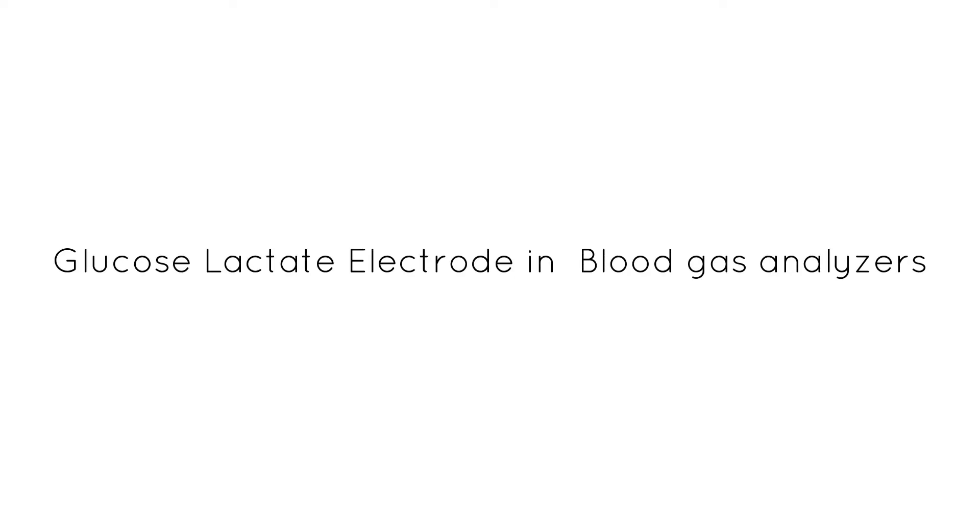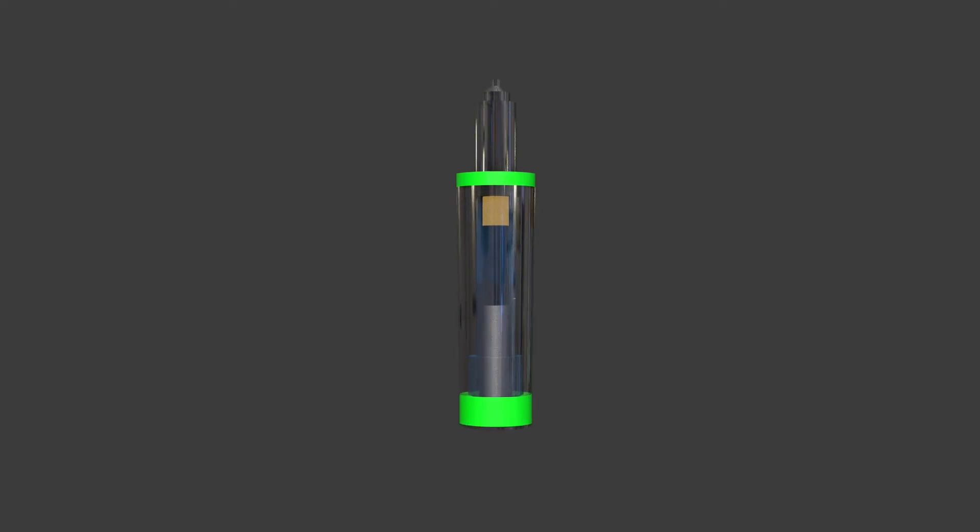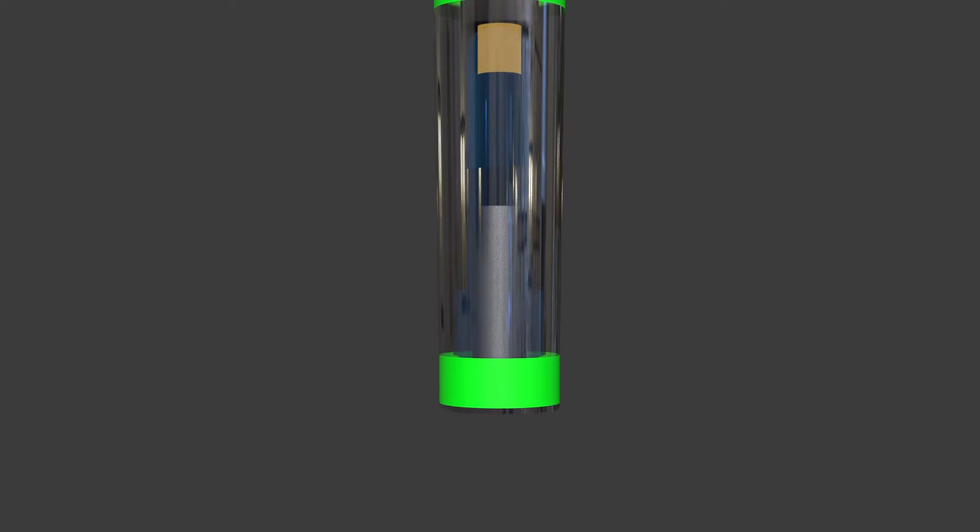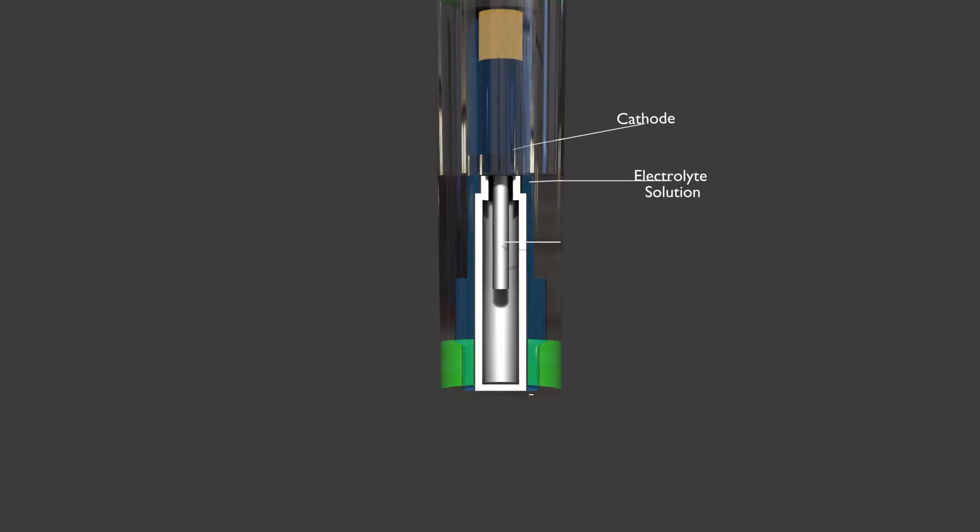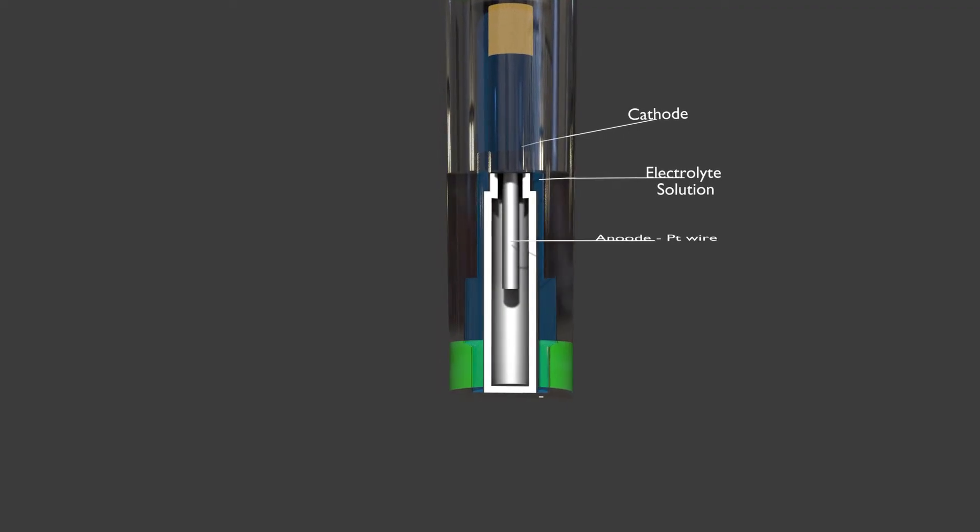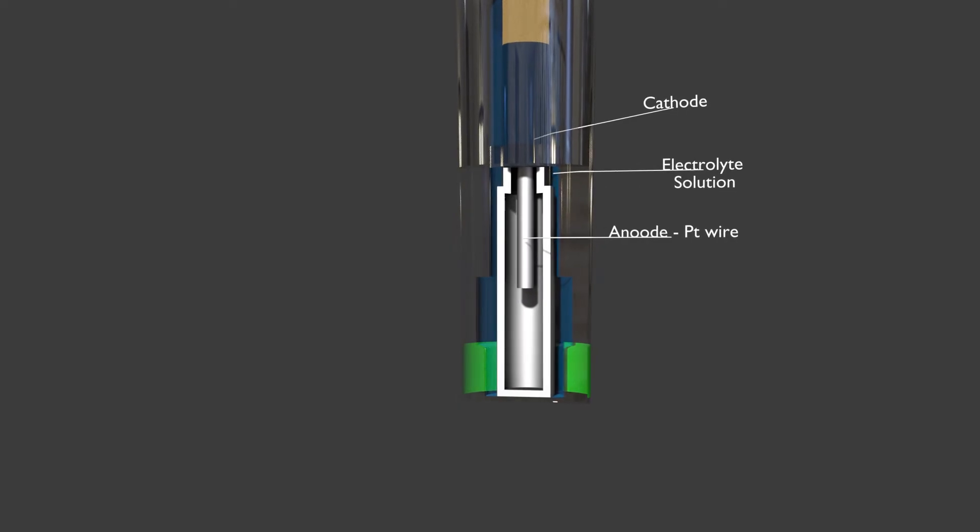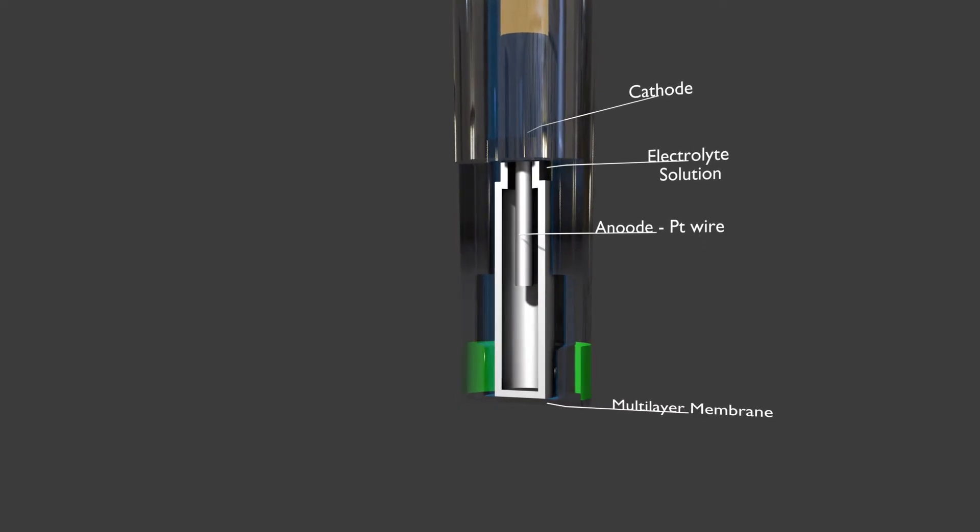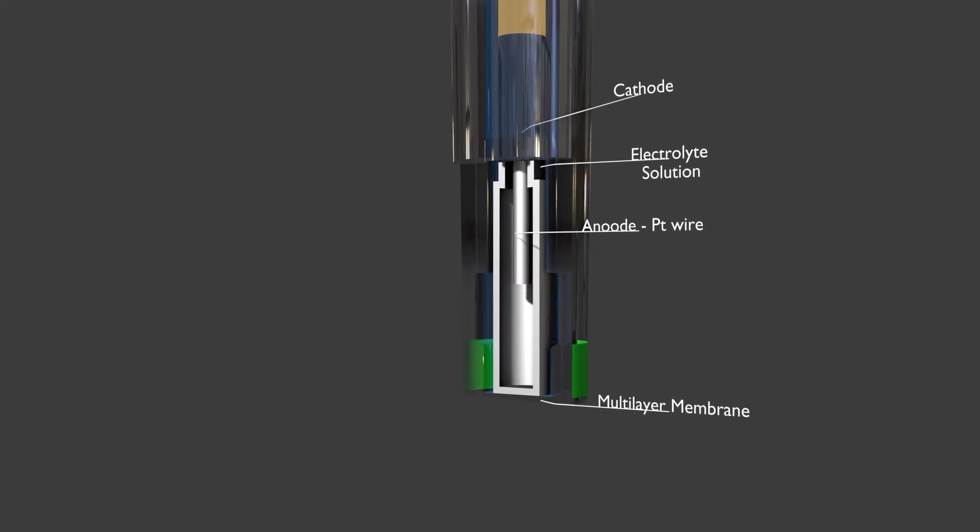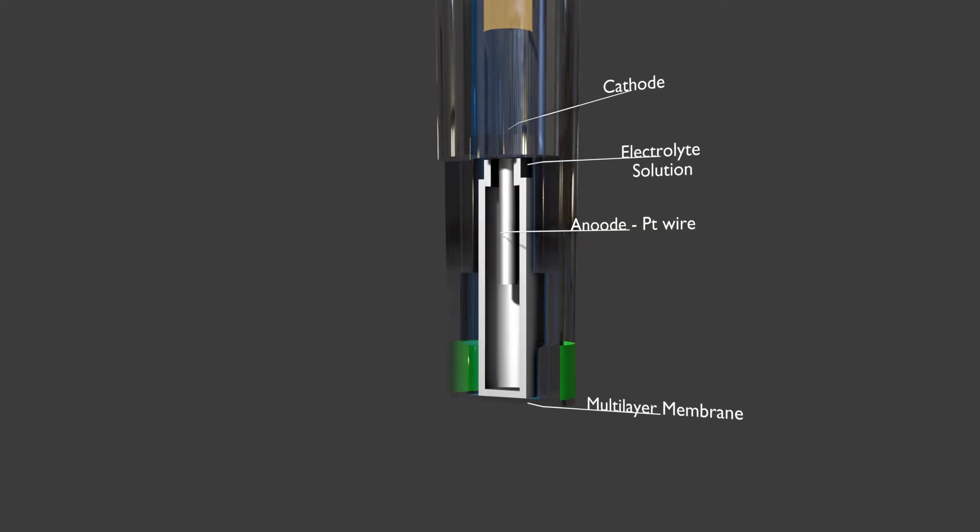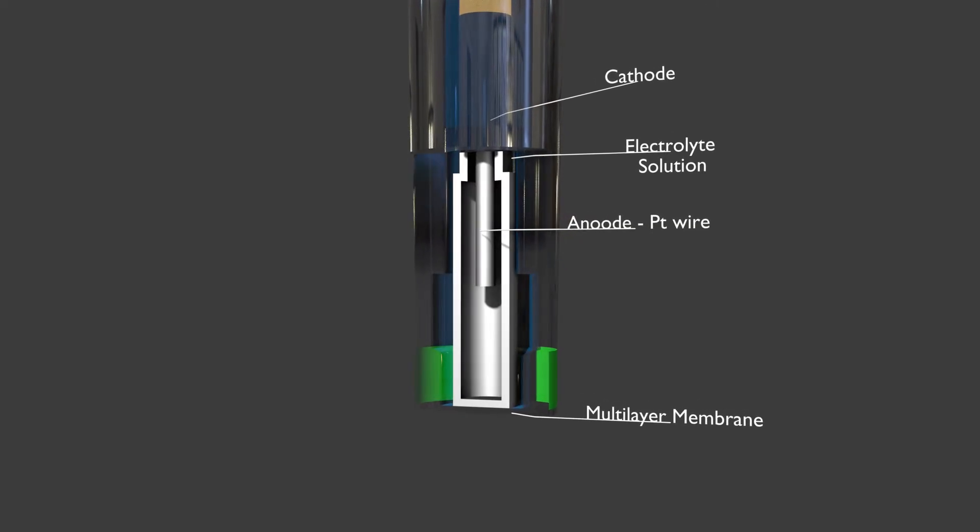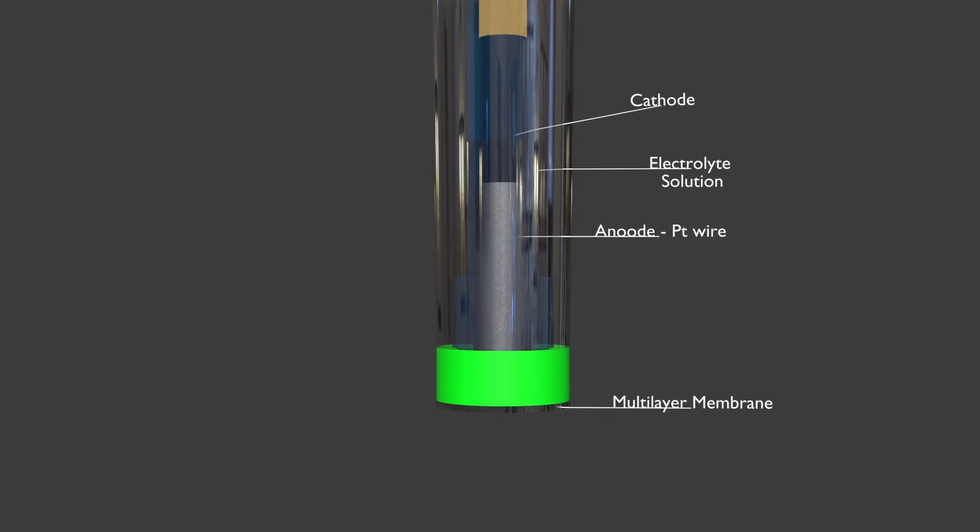The next electrode is used to measure metabolites like glucose and lactate. The measurement of glucose and lactate are vital by a rapid, reliable and reproducible means. These values are determined by the oxidation of H2O2 hydrogen peroxide. There are two electrodes in the electrolyte solution. It is important to note that there is a silver-silver chloride as cathode and a platinum as an anode, in contrast with the Clark electrode. Each electrode is then covered by a three-layered membrane. It measures current, determined by the degree of concentration of glucose or lactate, thus calibrated to read glucose or lactate.